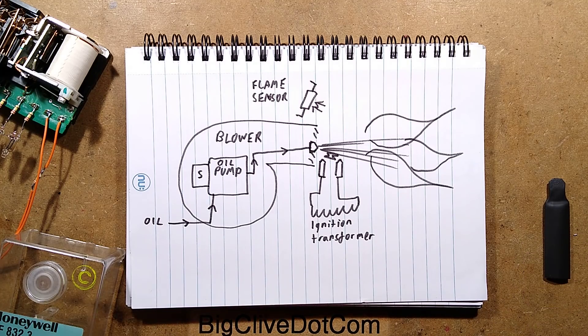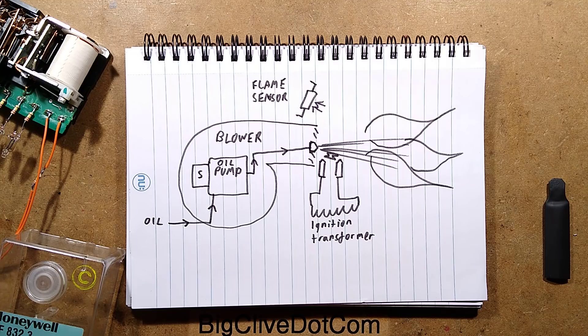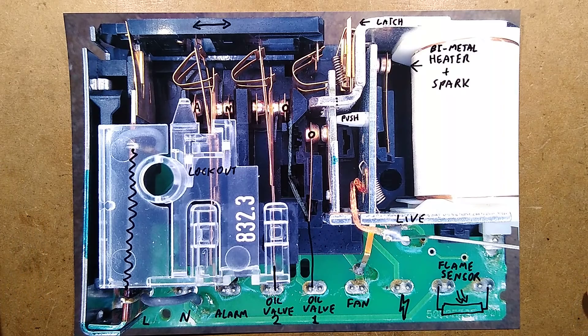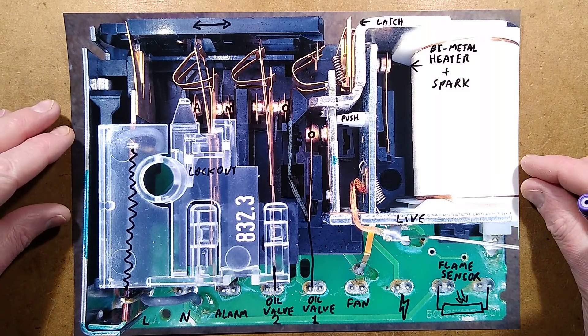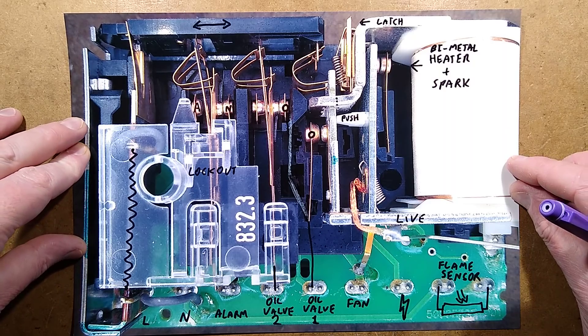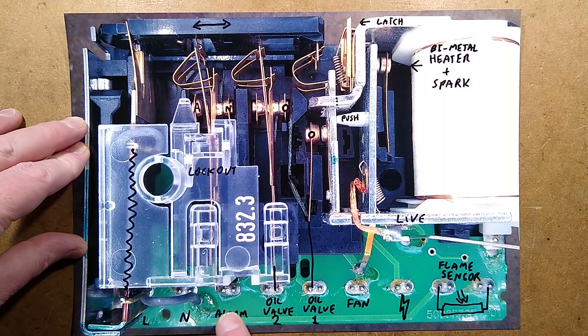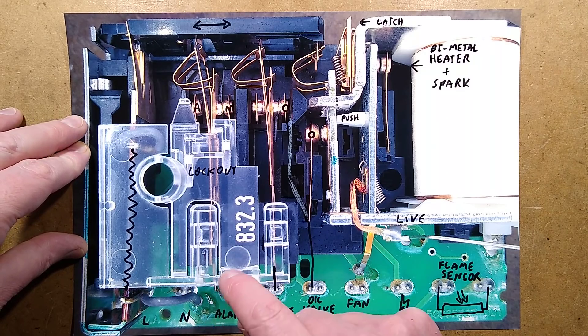If the flame goes out again, it will have another go at lighting it. If the flame goes out and stays out, it will automatically shut everything down and signal an alarm to the controller. It's all done in a very devious and clever way. Right, quick jump cut because I'm going to get the paperwork in to show you how this system operates.